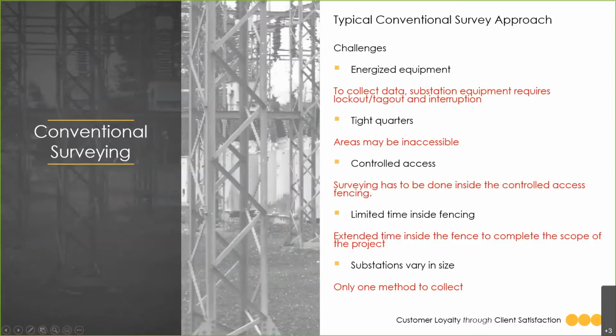First, we're going to look at a conventional survey approach and how it adds to the challenges I just mentioned. When working around energized equipment, collecting data requires lockout, tagout procedures, which interrupt the utility facility. This must be performed by qualified electrical workers, adding to the personnel needed inside the substation. At times, the surveyor isn't a qualified electrical worker, and the electrical worker isn't a surveyor, so there's a lot of opportunity for miscommunication and issues to arise. Another consideration in conventional surveying is the tight quarters of the substation.